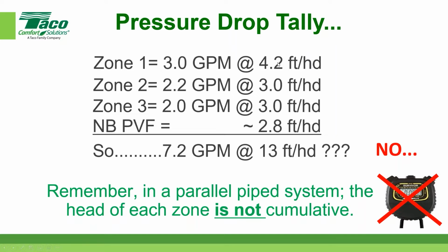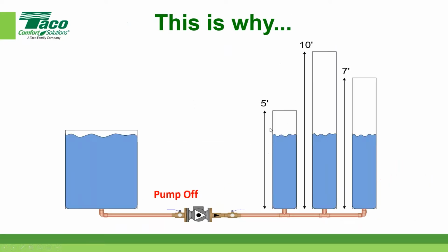So all you do is remember to use the higher number of the three. In this case, a 3-zone system. It could be a 7-zone system. You would take the higher number, and then any incidental pipe, valves and fittings in and around the near boiler piping, right? And then you add those numbers together. And this is why, okay?